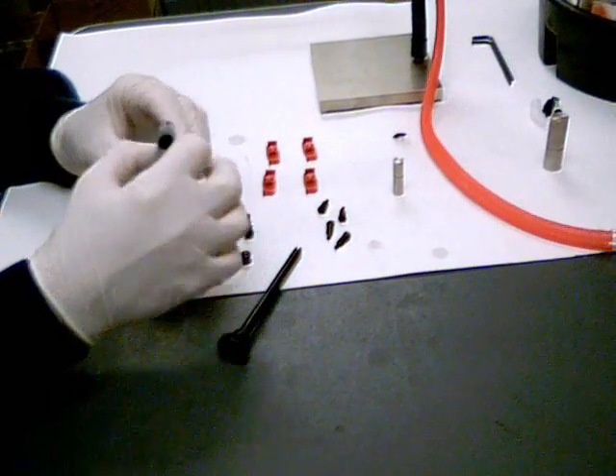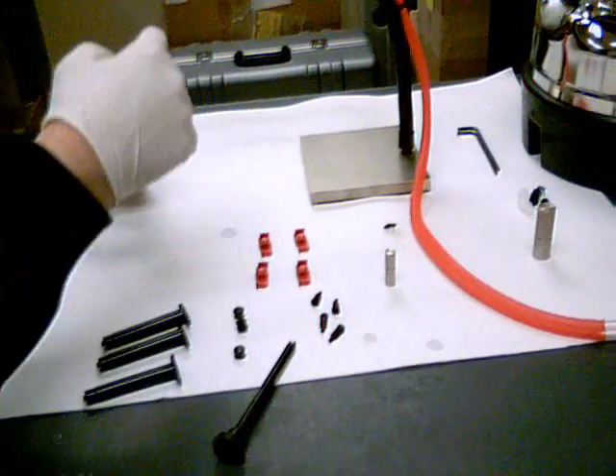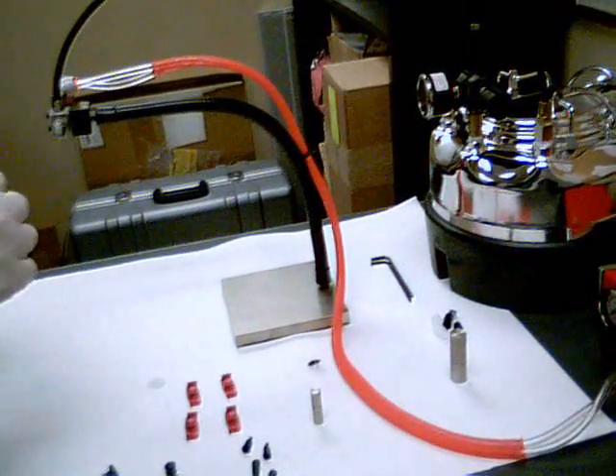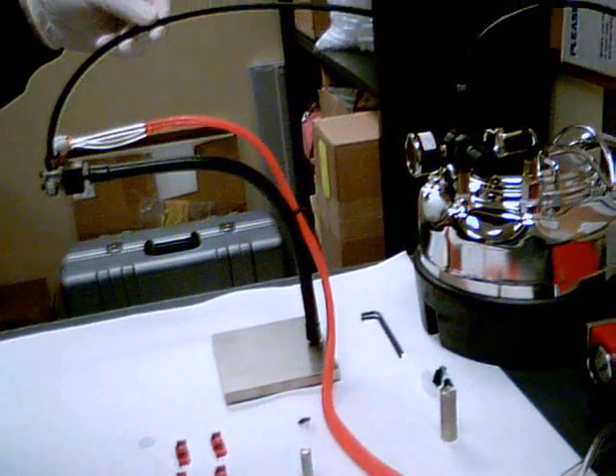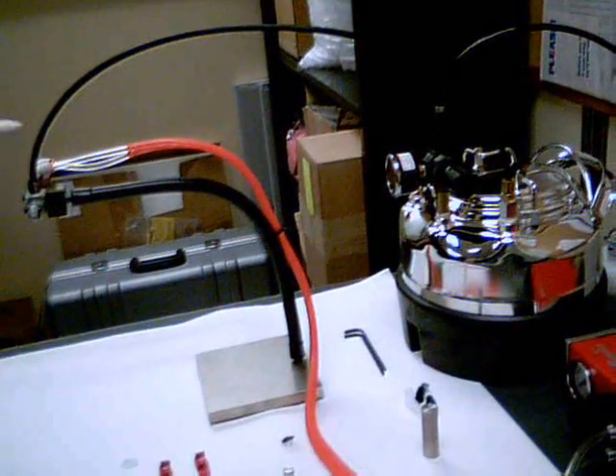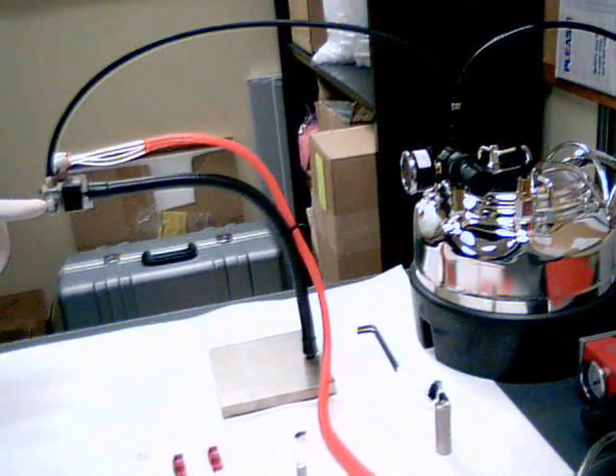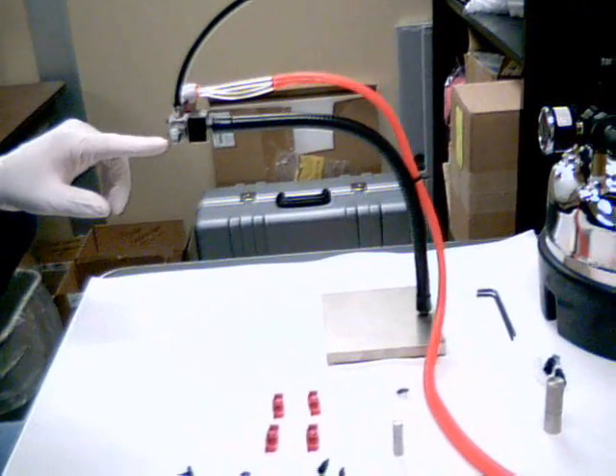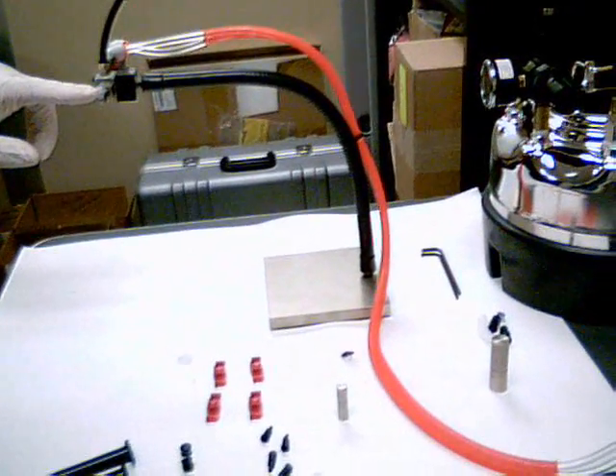Once that's all the way to the bottom, I've already purged all the air out of our liquid line here. I have fluid all the way up to our adapter, so this is an air-free system right now all the way up to this point.